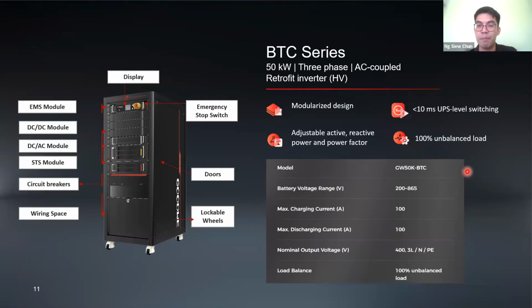So these are some of the parameters of the 50 kilowatt BTC inverters. The accepted voltage range for the battery is from 200 to 865 volts. The maximum charging current will be 100 ampere. Maximum discharging current will be 100 ampere as well. And the nominal output voltage will be 400 volts. So it is actually very suitable for our Malaysia grid, where we can connect directly to the LV connections.